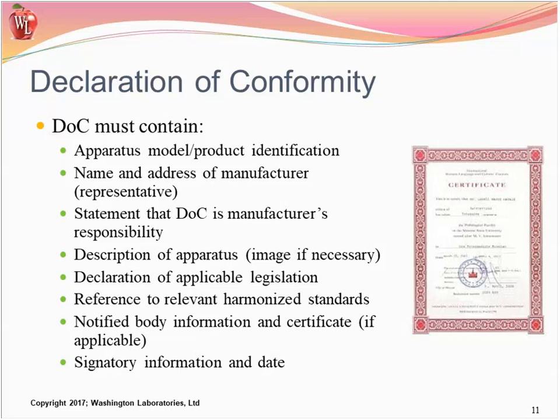Let's say you didn't follow the standards, but you went to a notified body and they provided you a test and evaluation program as an alternative because you can't follow the standard for whatever reason. That certificate from the notified body needs to be a part of your declaration, along with signatory information and date.